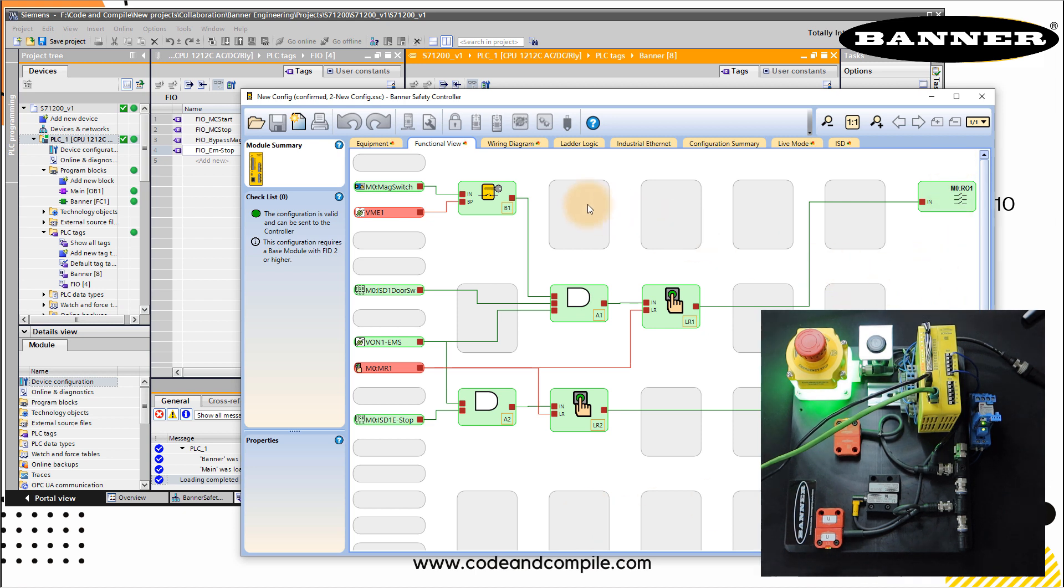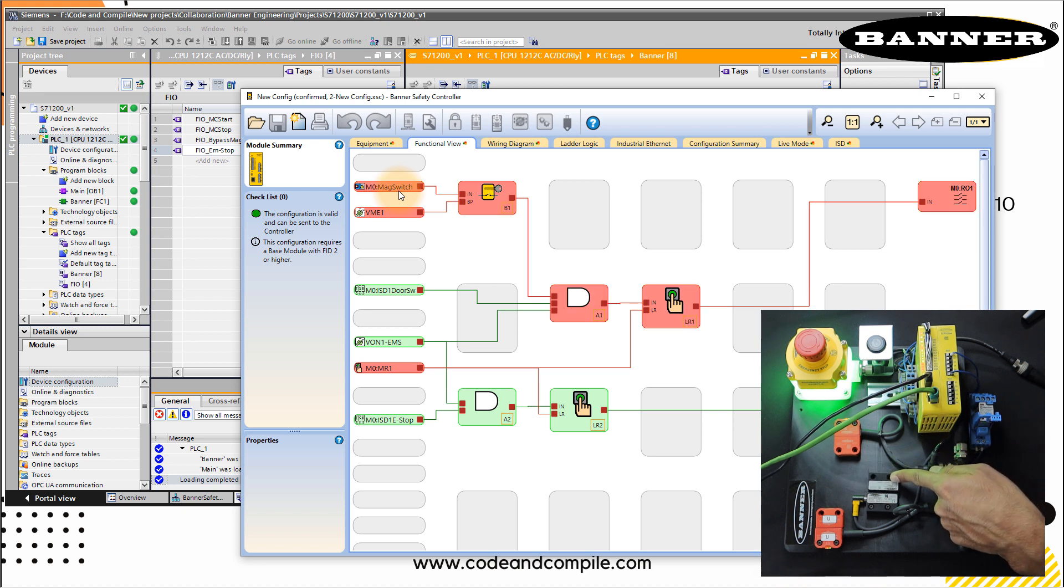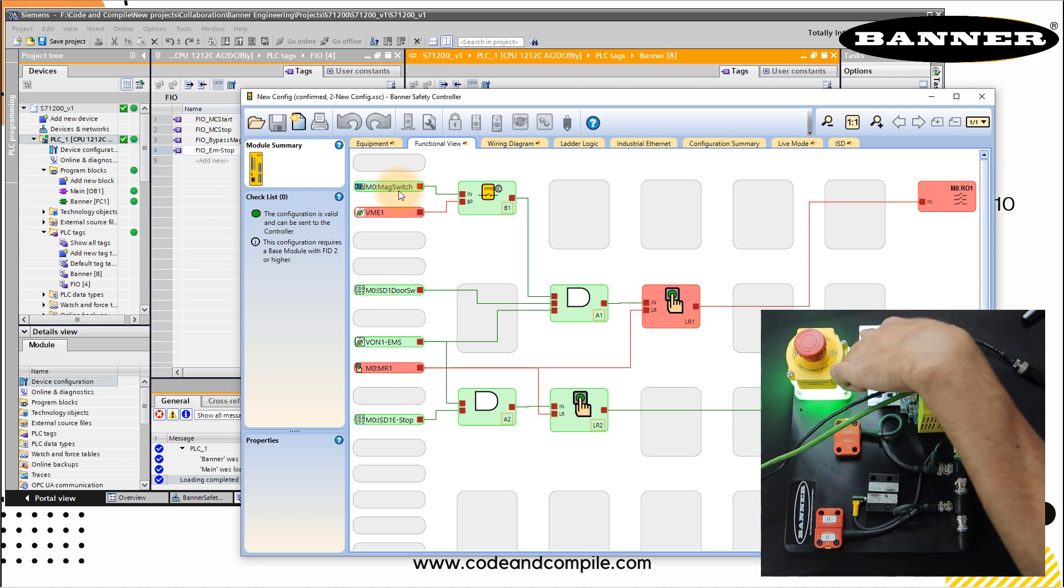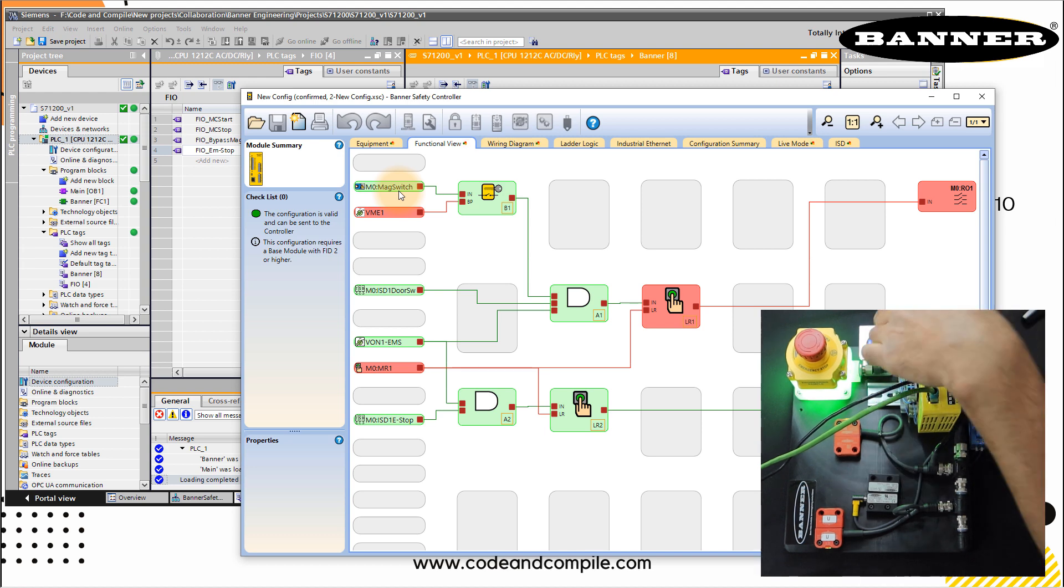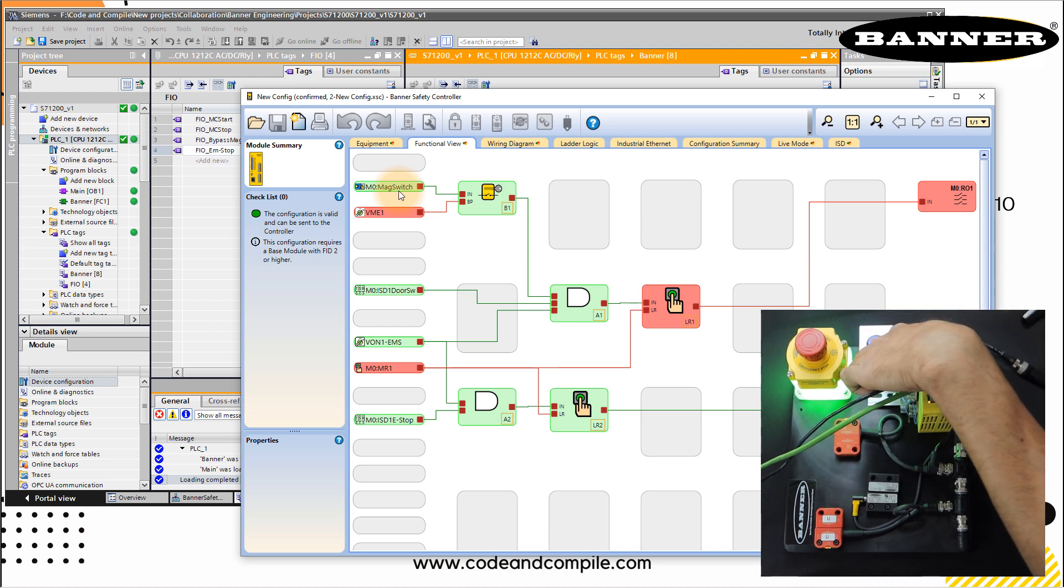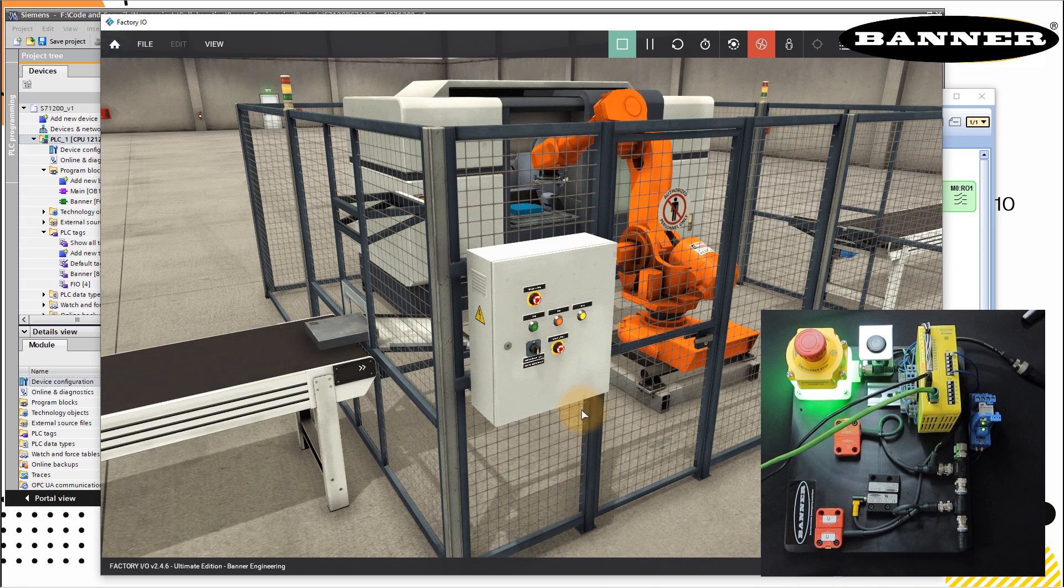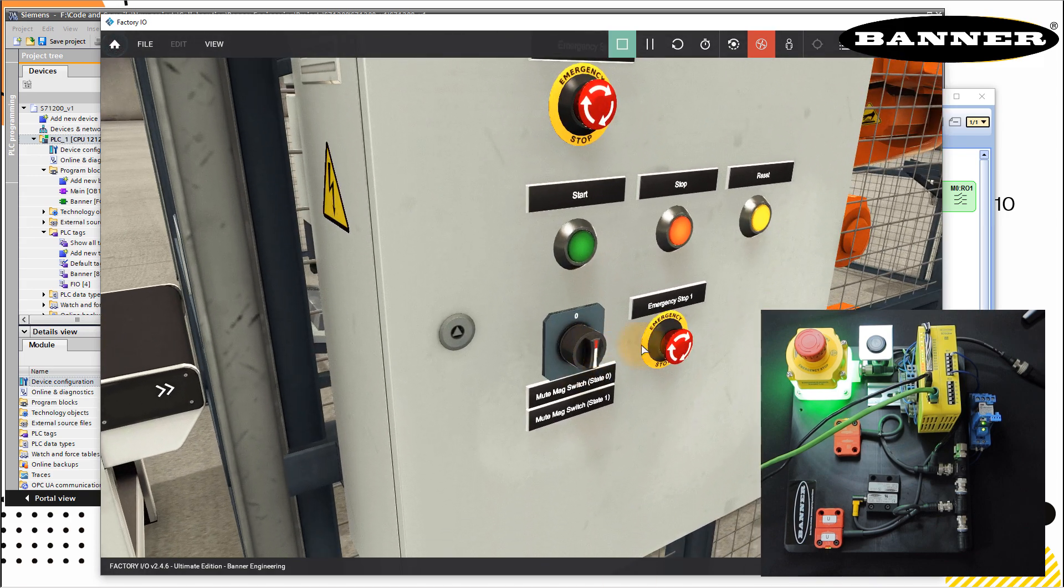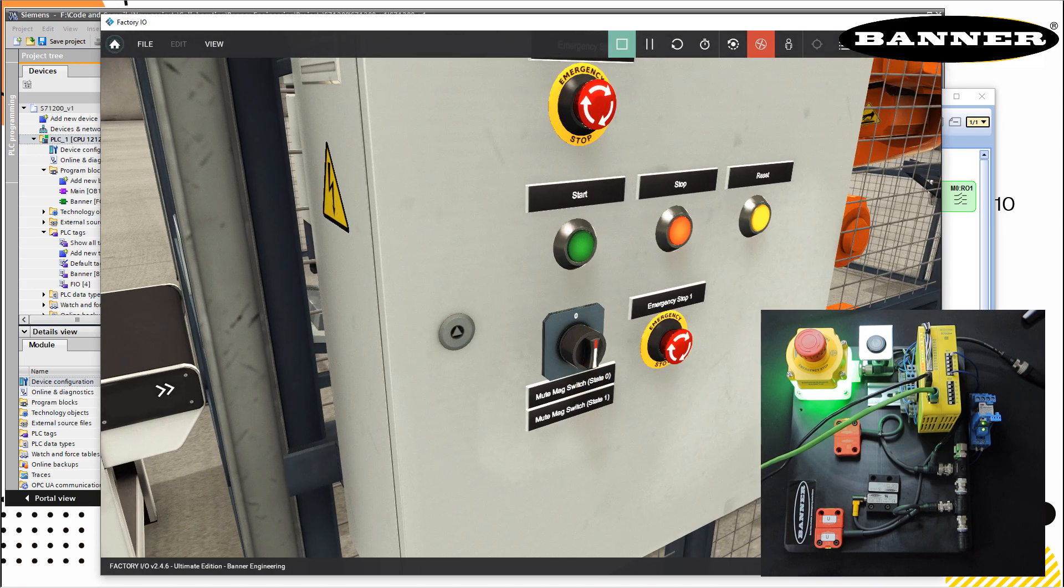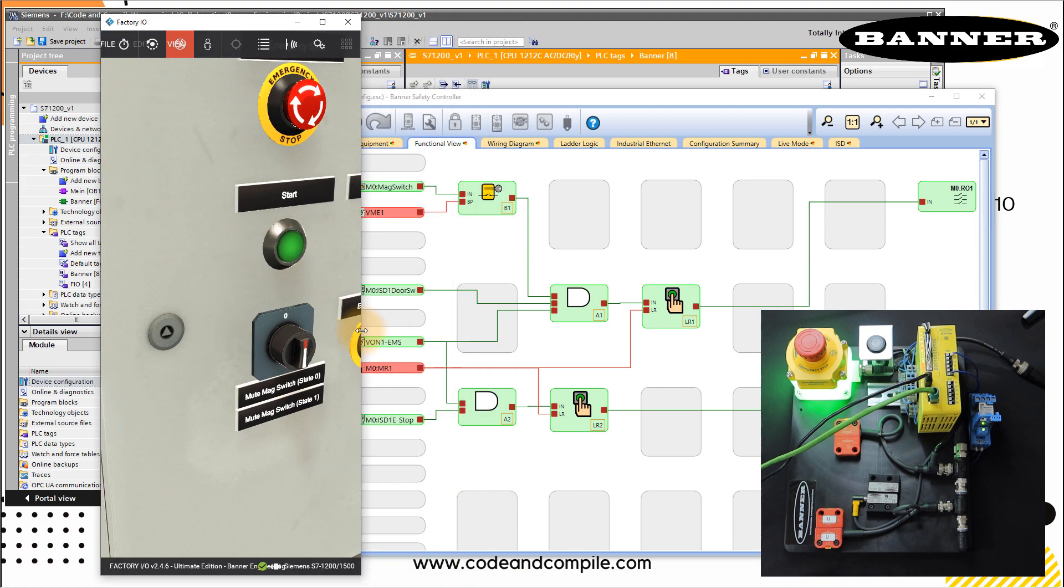So our task is to bypass this input. Let's see if we don't bypass, this is going to break the circuit. Like before, we knew that. Reset again. Now to bypass this magnetic switch, I need to actuate this one. So this I'm doing via selector switch, which is this one. So this is giving a signal to my PLC. Let's have a look.